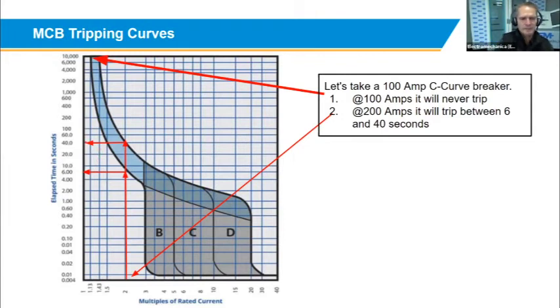That's according to the IEC table, and all products are tested according to this. So the Hager circuit breaker, 100 amp, putting 200 amps, will trip between 6 and 40 seconds. Keeping in mind, this is calibrated at 30 degrees C. So if you go in a panel where it's 40 degrees C, this product might trip faster at 200 amps because of the temperature inside your distribution board.